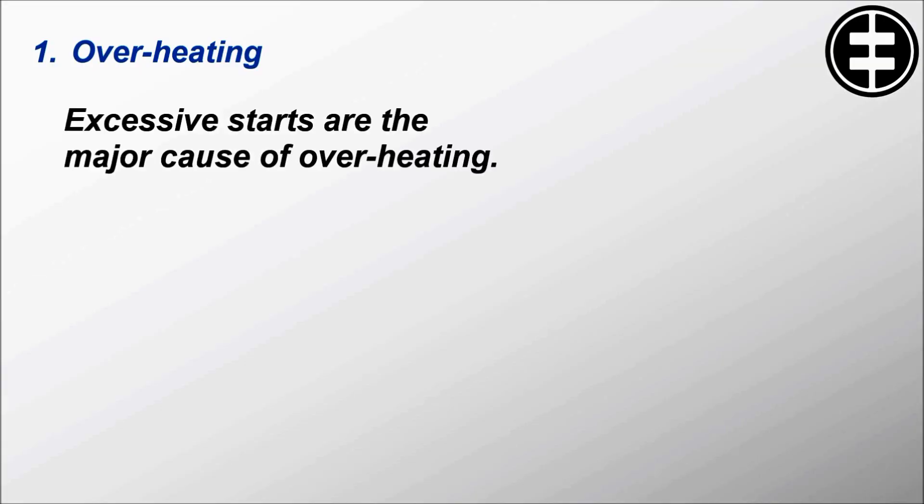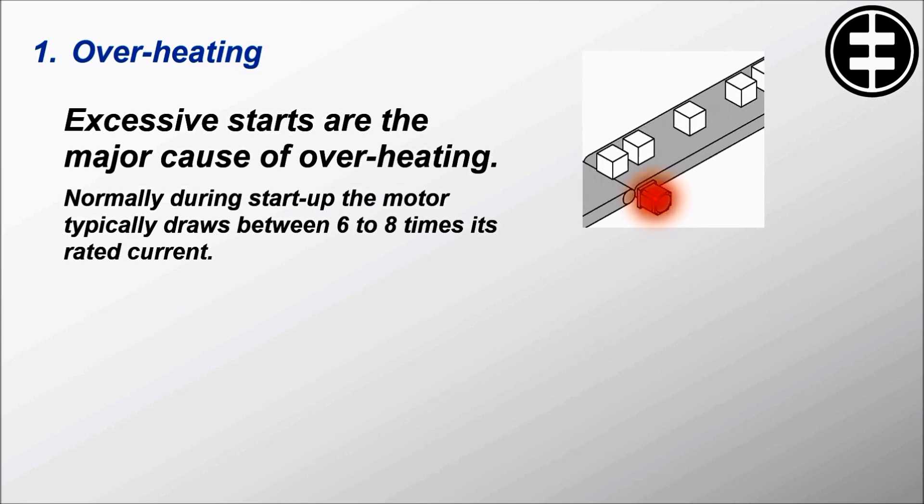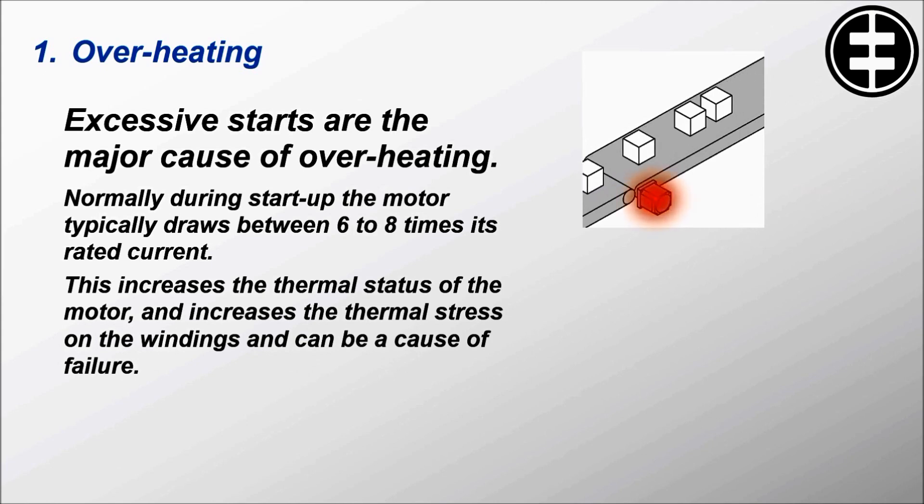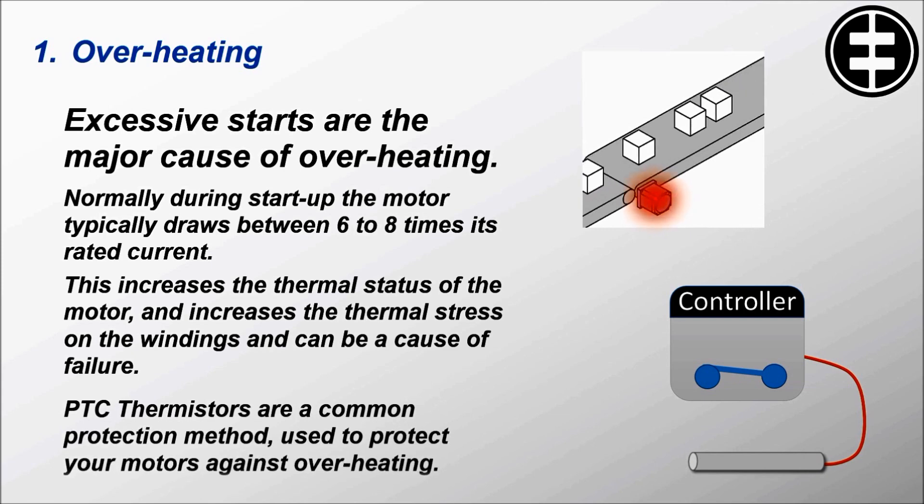Excessive starts are the major cause of overheating. Normally during start-up the motor typically draws between 6 to 8 times its rated current. This increases the thermal status of the motor and increases the thermal stress on the windings and can be a cause of failure.